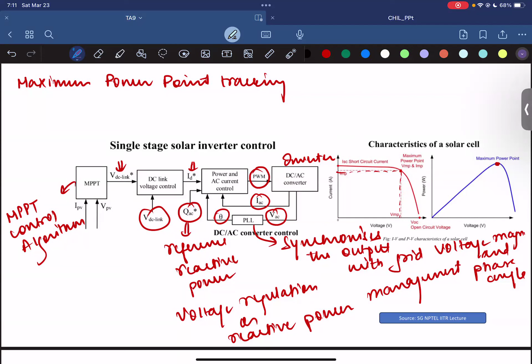Yes, but what you're doing is trying to mimic your grid output reference. So whatever your grid output reference is, that's your real power. I'm not talking about how your inverter is behaving—the DC, the solar, is producing output at a DC rate, and it's real power that it's producing. So you want this real power to flow from a high reference voltage point to a lower reference voltage point. That is how you are maintaining your DC link voltage.